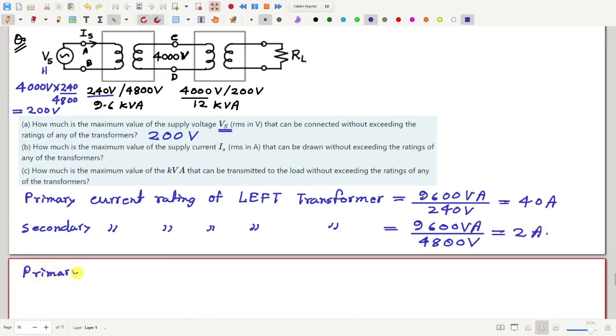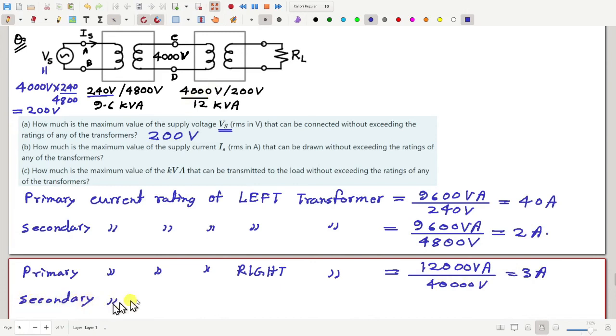Similarly, the primary current rating of the right side transformer is how much? The kVA rating is 12,000 volt ampere divided by the primary voltage rating of this second transformer, 4000 volt. So that means this is 3 ampere. And similarly, the secondary current rating of the right side transformer will be 12,000 volt ampere by secondary rated voltage, 200 volt. So this is 60 ampere. These are the maximum allowable currents in the primary of the first transformer, secondary of the first transformer, then primary of second transformer, and secondary of the second transformer respectively.